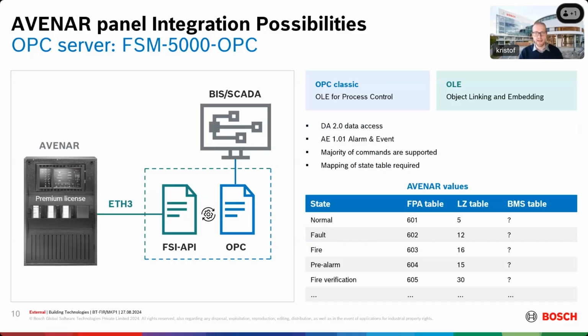We are using Data Access 2.0. This is actually to fill out or to create the Excel sheet, as a figure of speech. And Alarm and Events is actually updating the status in that Excel sheet. Also here, the majority of commands are supported. And something which is not standardized in OPC is states. So the protocol is standardized, but the meaning of the states is flexible. And for that, you need to make a mapping table.